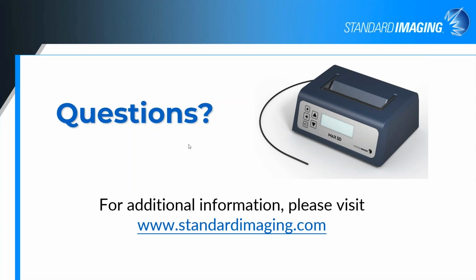For small field scanning, do you need a reference signal? Will it improve the signal to noise ratio? You can scan with or without a reference detector. It really doesn't matter for this one because you're scanning slowly enough that the difference in one pulse here or there doesn't make a big difference. Most people actually prefer to scan without a reference signal just because it's a little simpler for this one, but you can do it either way.